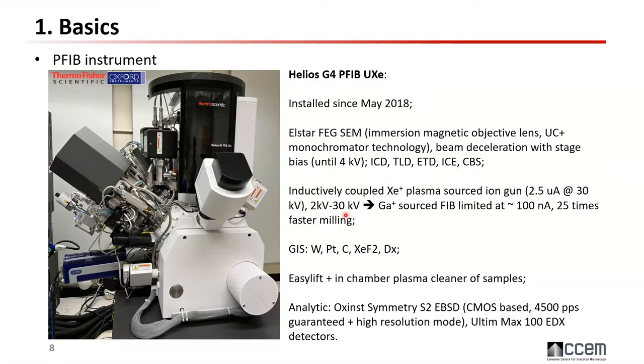What is special about the plasma FIB xenon source is that we can achieve 2.5 microampere beam current. Comparing to the traditional gallium source which is limited to about 100 nanoampere, you are basically 25 times faster. The instrument also has an EasyLift which is fully controlled by the mouse, and a chamber plasma cleaner for samples.